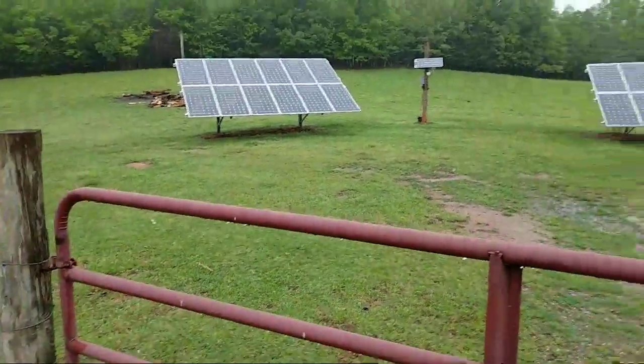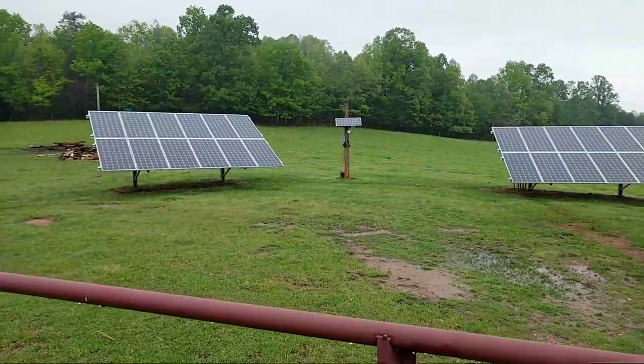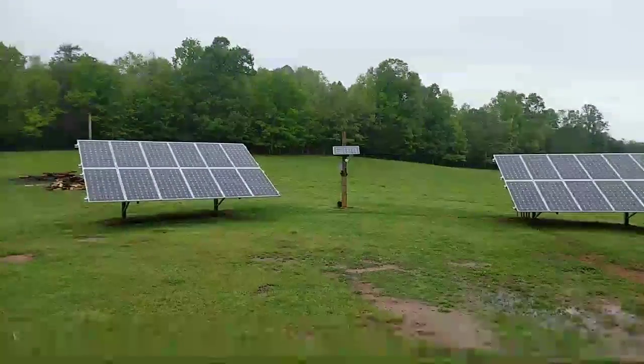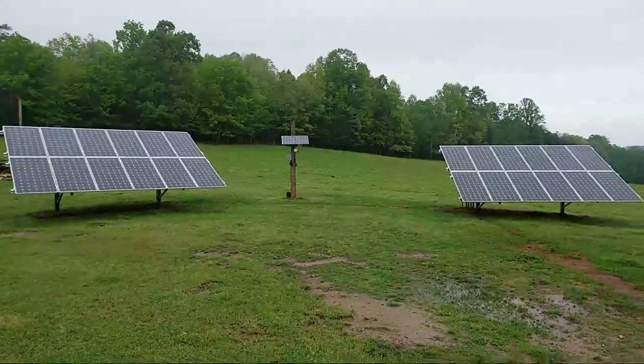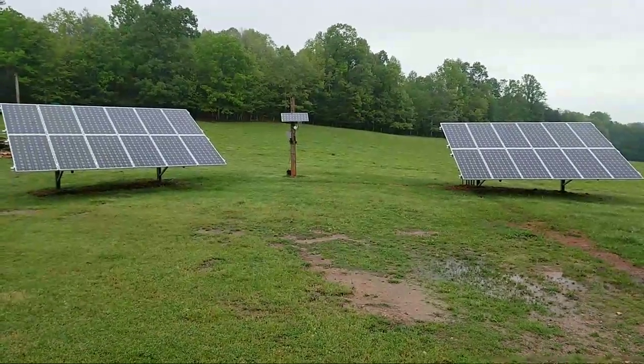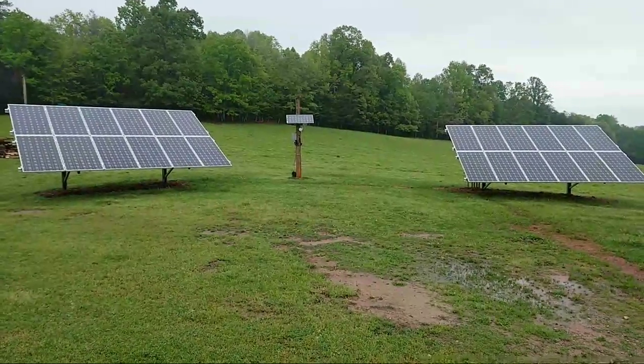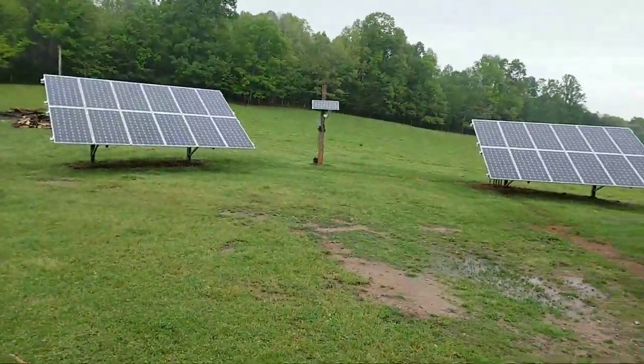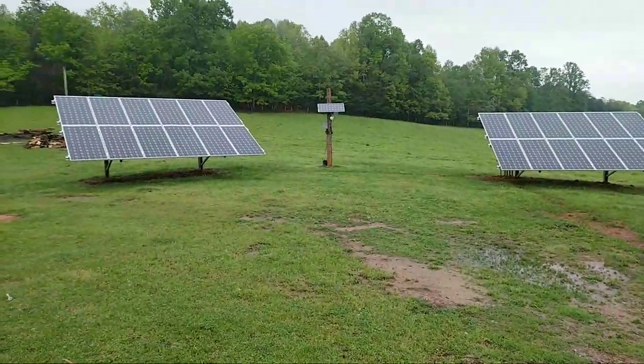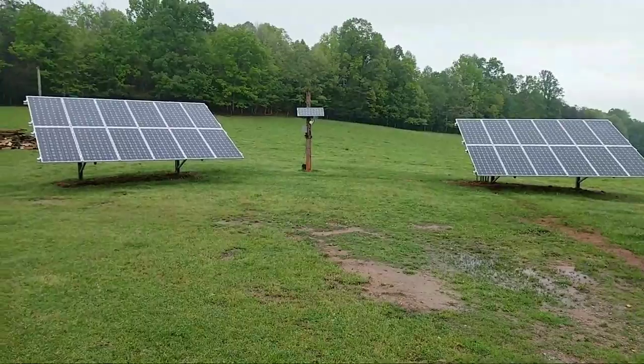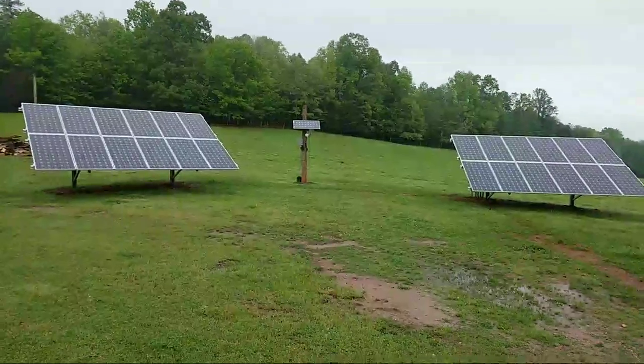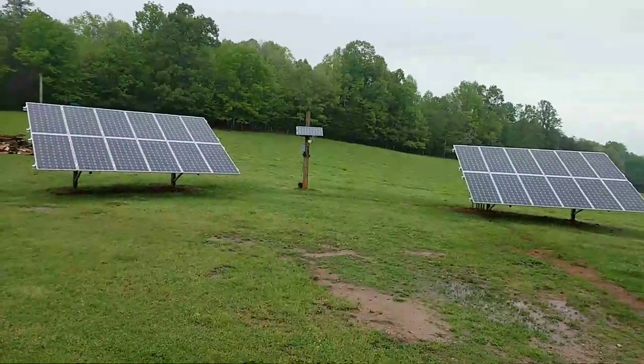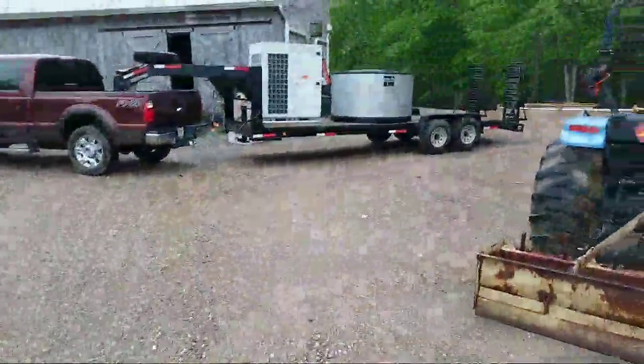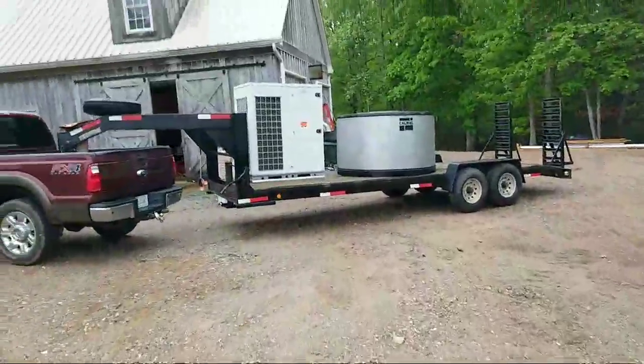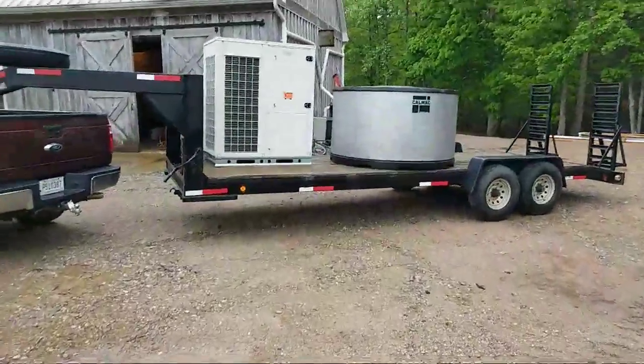Solar's doing great, and I've run the chiller off of this array. I don't have any problem running it, but I'm going to add some more inverter capacity with the Pika Energy 7600 watt inverter. This is my system: here's a 48 volt, but the Pika is a 380 volt, and it's very efficient, much smaller inverter. Everything's smaller because the voltage is so high, and we can get away with a lot, and do a lot longer DC runs too, so the arrays can be farther away without having to go crazy on your wire size.